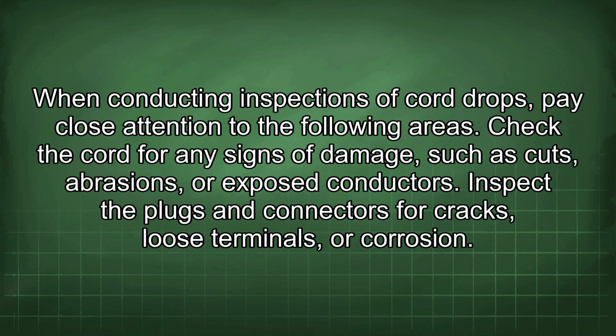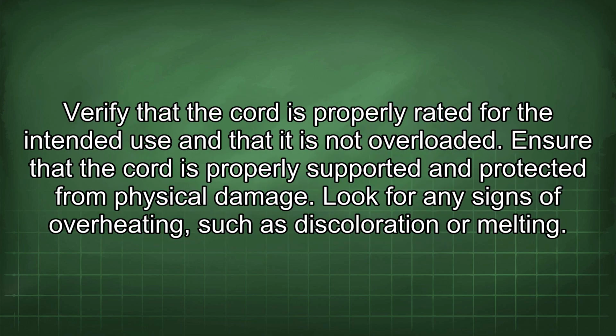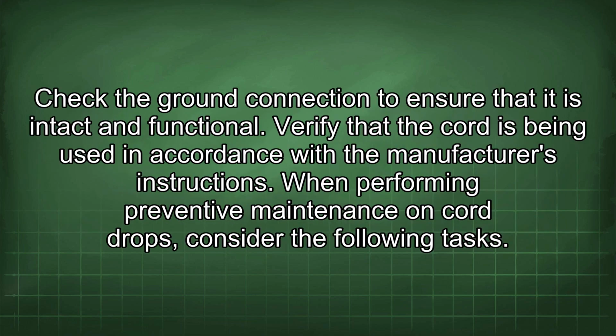When conducting inspections of cord drops, pay close attention to the following areas. Check the cord for any signs of damage, such as cuts, abrasions, or exposed conductors. Inspect the plugs and connectors for cracks, loose terminals, or corrosion. Verify that the cord is properly rated for the intended use and that it is not overloaded. Ensure that the cord is properly supported and protected from physical damage. Look for any signs of overheating, such as discoloration or melting. Check the ground connection to ensure that it is intact and functional. Verify that the cord is being used in accordance with the manufacturer's instructions.